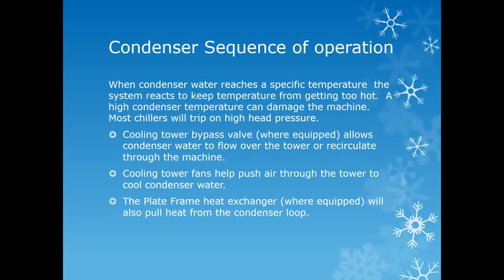On the other side of the chilled water system, when the water reaches a specific set point the system will react to help keep the temperature from getting too hot. Generally if the condenser water gets too hot the chiller can go out on a high head pressure, which can damage the machine. Most chillers do have some type of safety designed to protect them. The cooling tower bypass valve, when equipped, will open flow to the tower to flow the condenser water over the cooling tower and remove the heat. The cooling tower fans help push air through the tower to additionally cool the condenser water. A plate frame system, if equipped, will also help to pull the heat from the condenser loop.